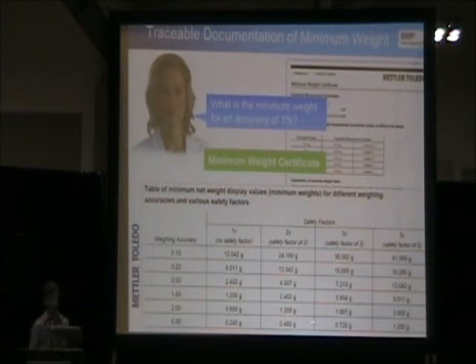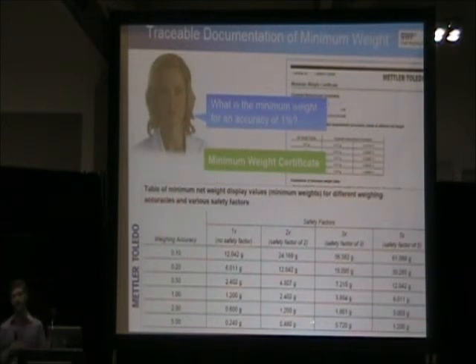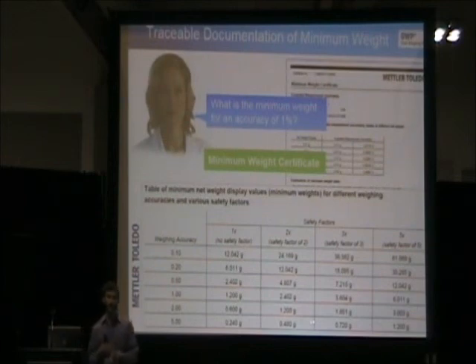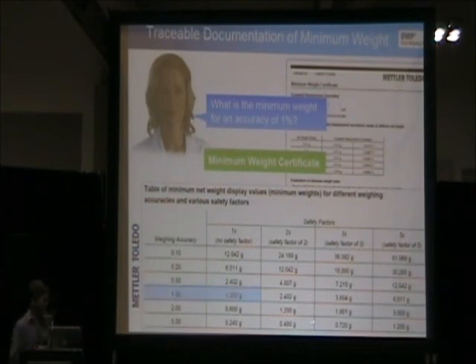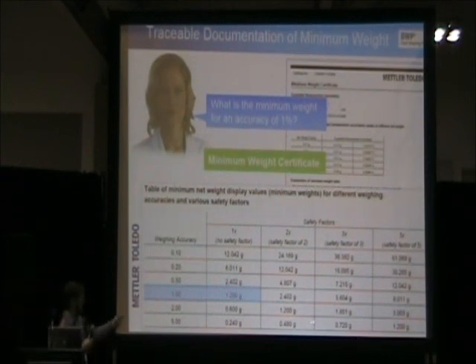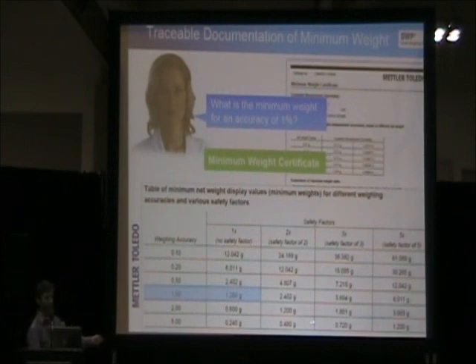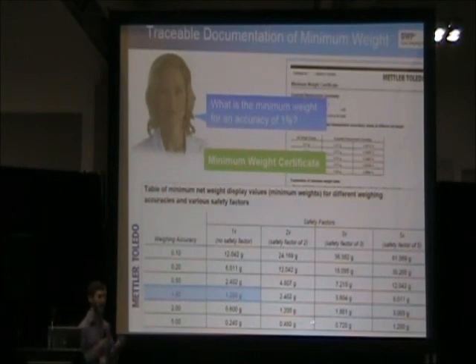If you stay at 30 milligrams, you don't give yourself a safety factor, and on that same Tuesday there's a lot of static in your facility, you run the risk of going below that 30 milligrams in terms of the uncertainty measurement, and in turn you will not be meeting your process tolerances or your accuracy limitations. So as an example here, let's say your weighing accuracy is 1%, plus or minus 1%. You establish your minimum weight, which ends up being 1.2 grams. This table here will show you what your minimum weight will actually be by applying a safety factor. Very simply put, you will take your minimum weight and you will times it by a certain value.